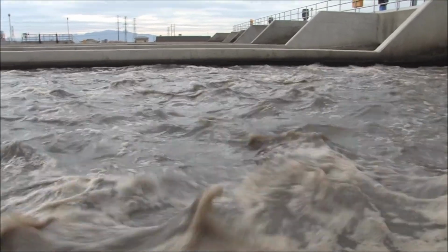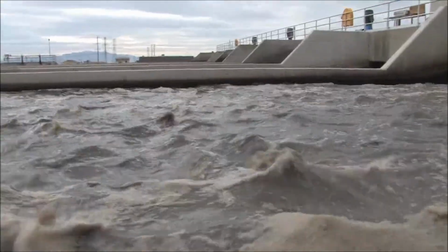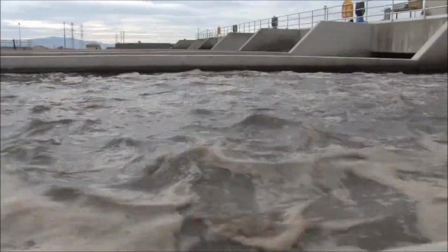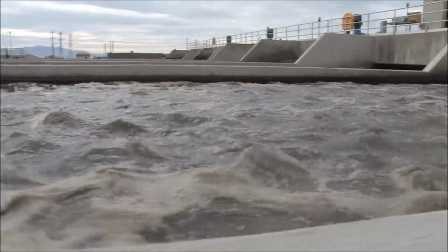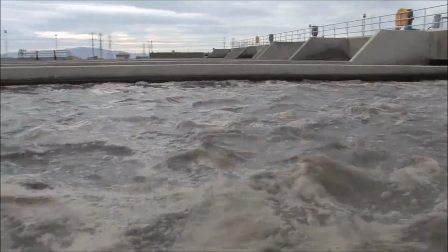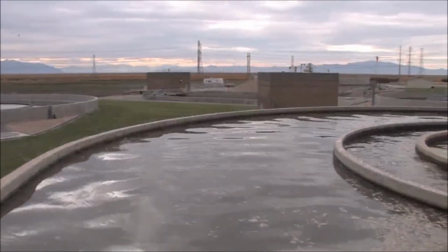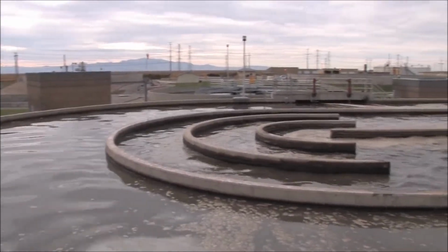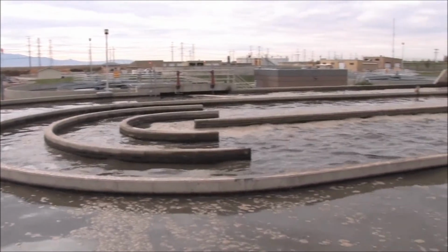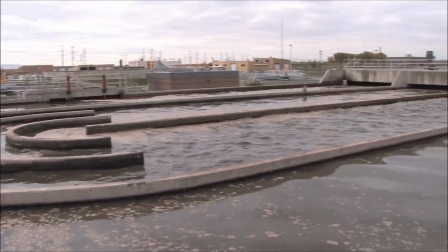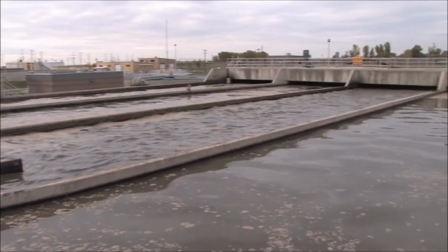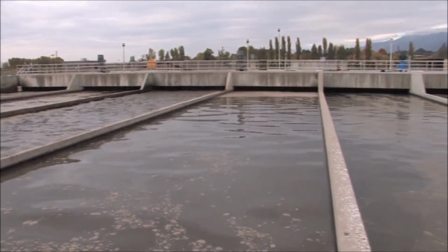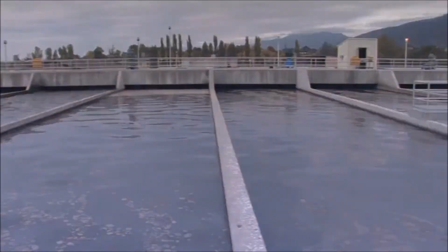As mentioned, nitrification is a very oxygen-hungry process. As a comparison, in order to remove 1 pound of BOD, 1.2 pounds of oxygen are required. However, to reduce 1 pound of ammonia to nitrate, 4.6 pounds of oxygen are required. Since getting dissolved oxygen into wastewater is a very energy-intensive process, it would benefit every treatment plant's electrical bill if they didn't aerate more than they needed to. Over-aerating does nothing to improve the process. It really is flushing money down the toilet.